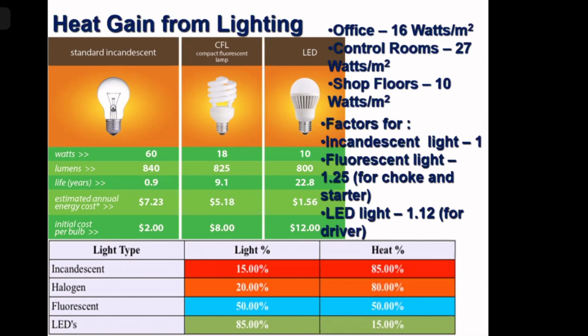They have given the load straight away, but you have to multiply this lighting load. If you are using an incandescent light, so if you are using a 60 watt light, all of the 60 watts comes as heat. Even the light part comes as heat. Fluorescent light, if you are using an 18 watt light for the same amount of lumens, you will otherwise use 60 watts. So for incandescent light, for some amount of lighting, you consider 60 watts as the heat load.